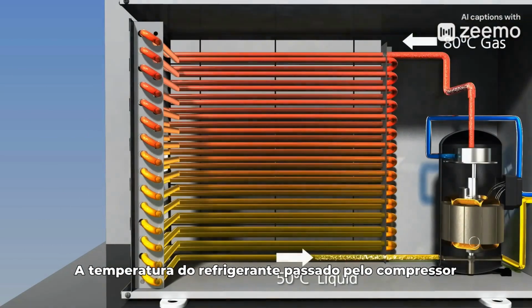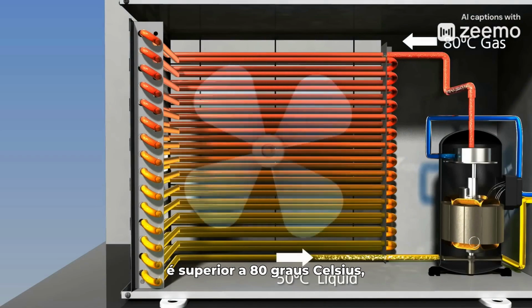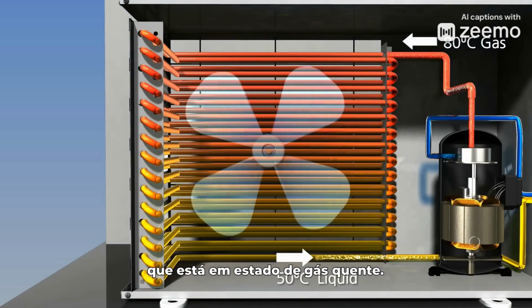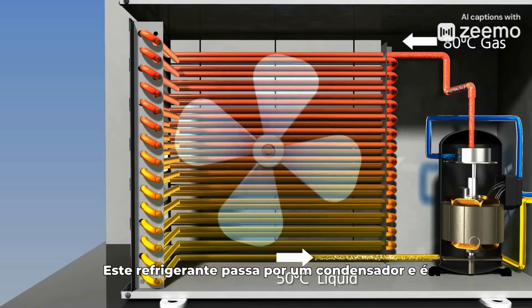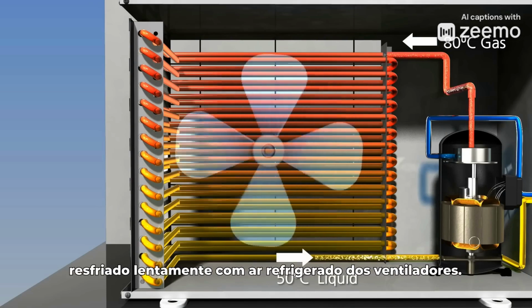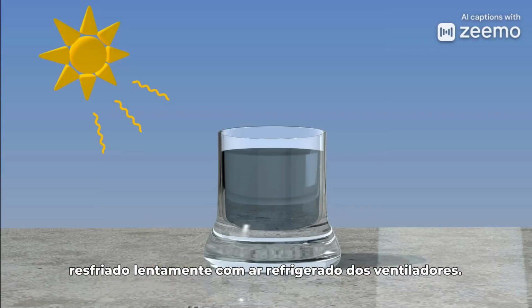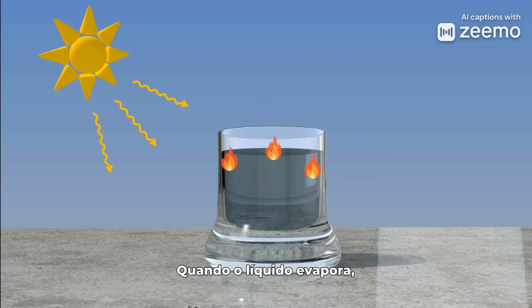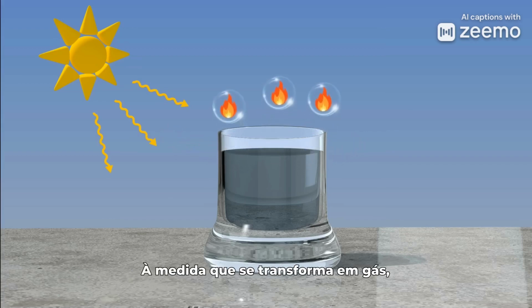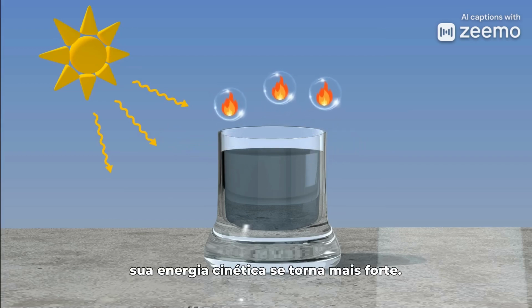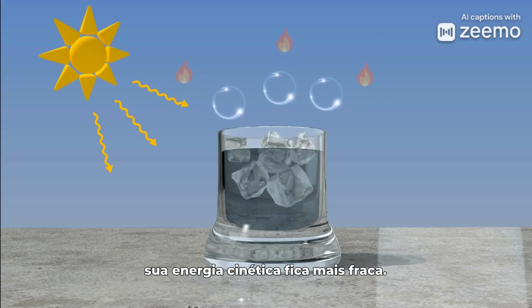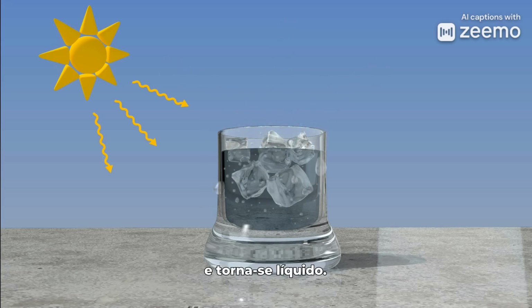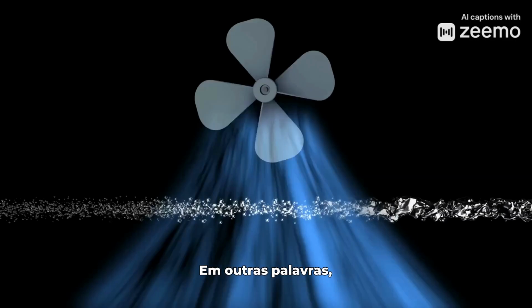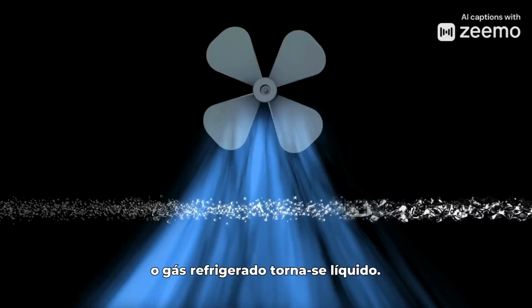The temperature of refrigerant passed through the compressor is above 80 Celsius, which is a hot gas state. This refrigerant passes through a condenser and is cooled down slowly with chilled air from fans. When liquid evaporates, it absorbs heat and becomes gas. As it transforms into gas, its kinetic energy becomes stronger. When the gas loses heat, its kinetic energy becomes weaker and it becomes liquid. In other words, chilled gas becomes liquid.